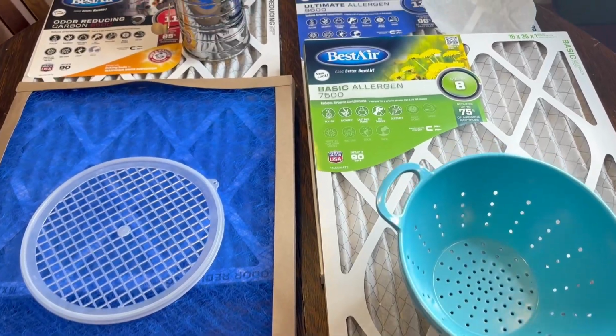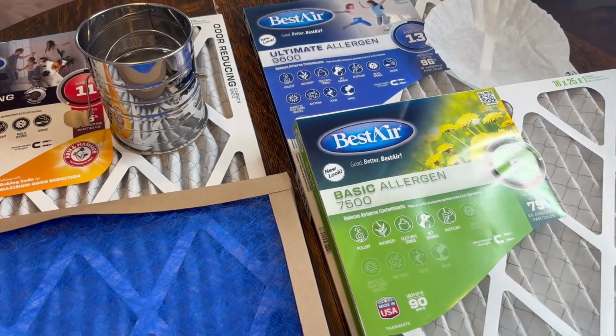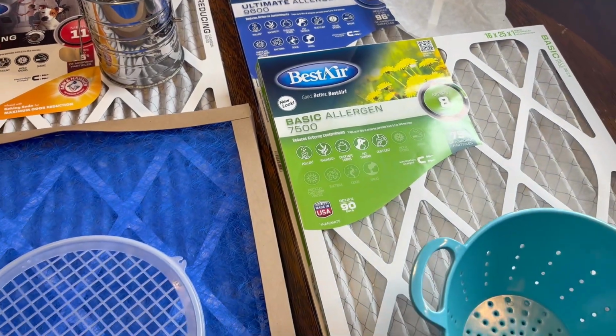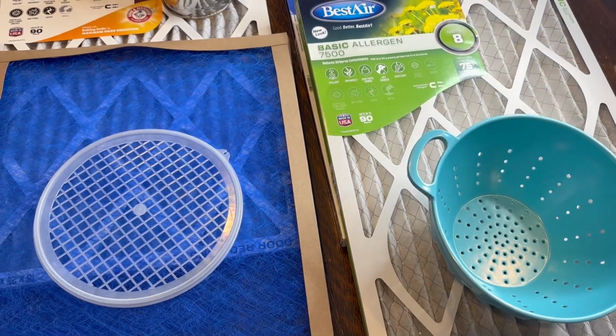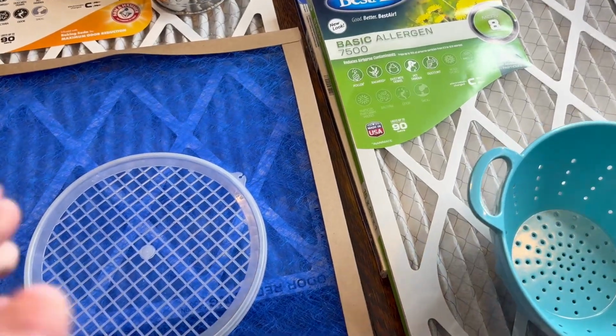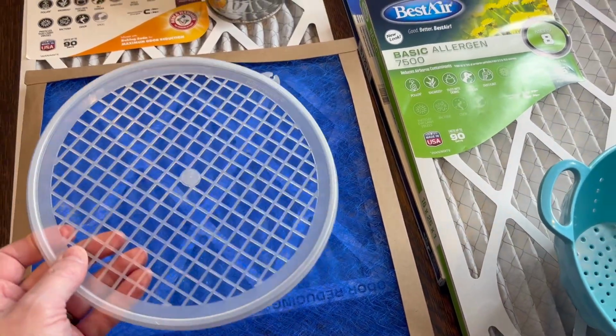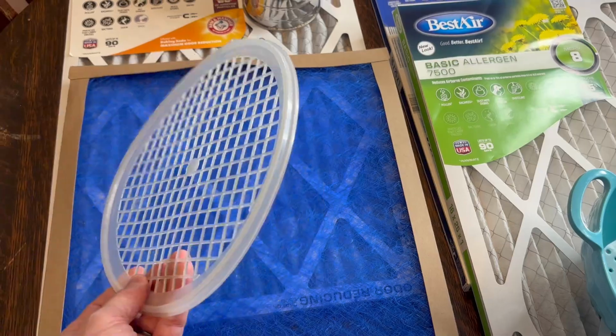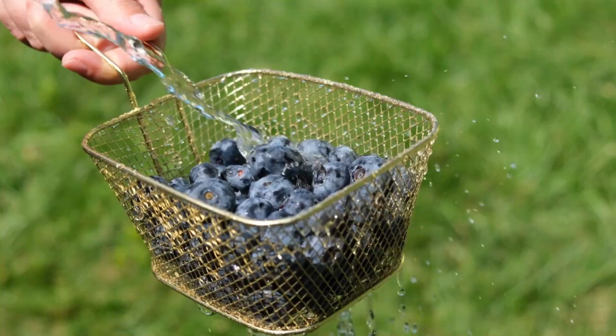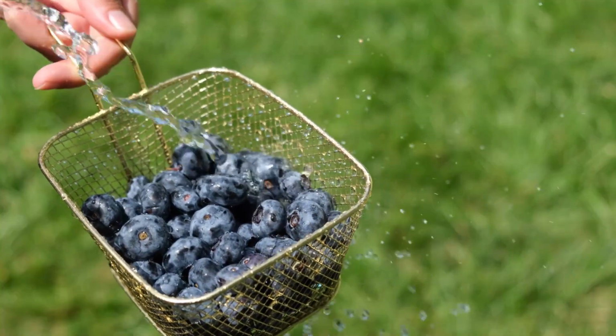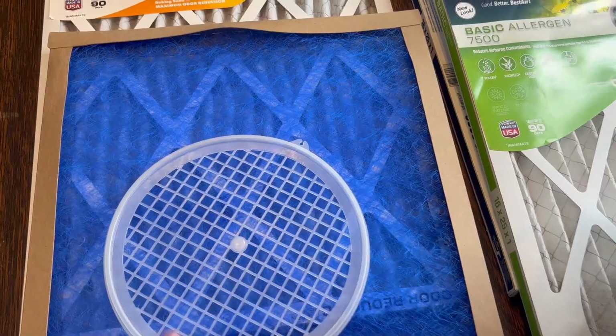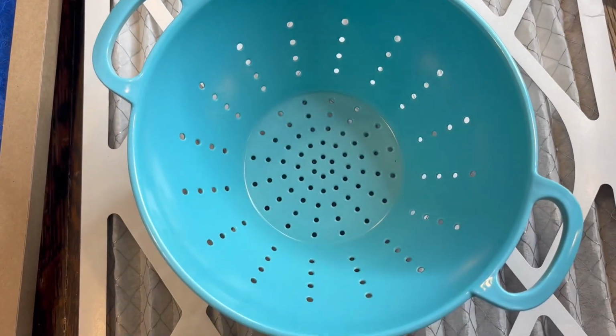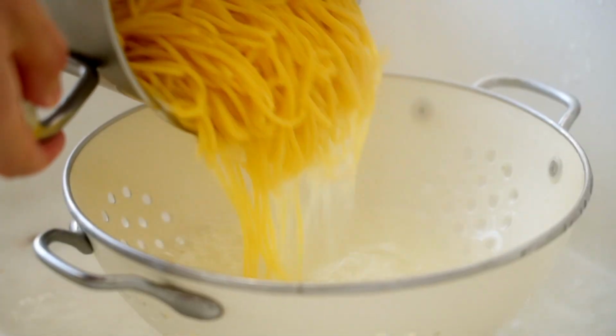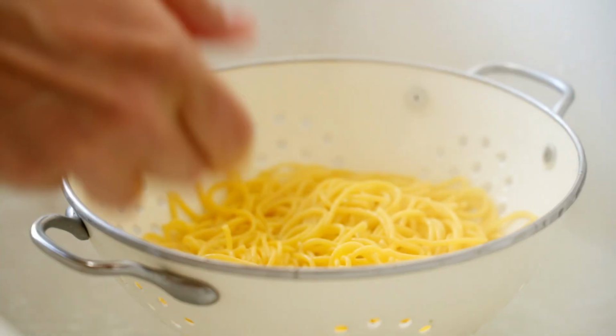And we all love these cheesy analogies, so we're using kitchenware just to visualize filter efficiency and flow restrictions. Obviously, our MERV 2, more flow, less filtration. And so we could probably filter out some berries here with this strainer lid, but anything smaller is going to flow through. Then we've got our MERV 8. We've got a pasta colander. We can strain out pasta. If we're trying to strain out rice, that's going to fall through.